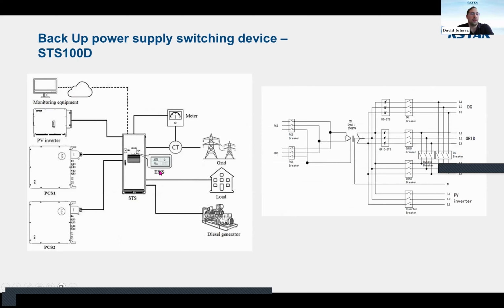There is a drawing of the 100D system, so we can see there is a separate connection for the diesel generator. For the 2 PCS, it can go up to 5 PCS for the 250, and it has a separate connection for the PV inverter. So for the connections, it has the separate connection for the diesel generator, the PV inverter, the grid, the load, and the number of PCS in case we use the 100D or the 250D.